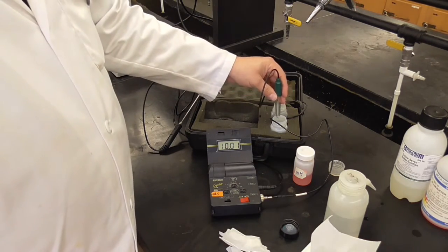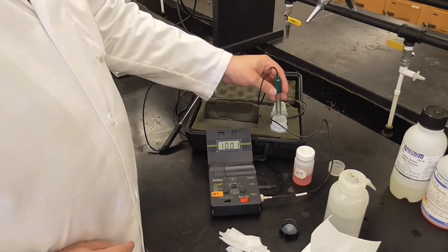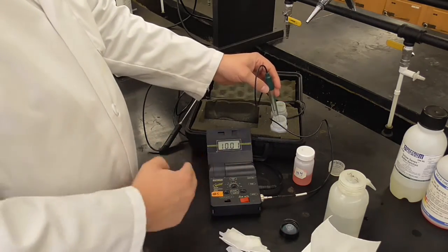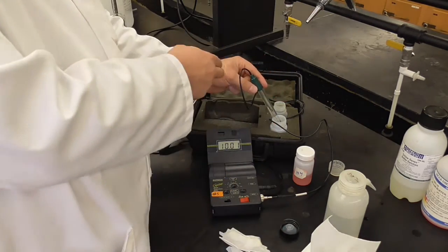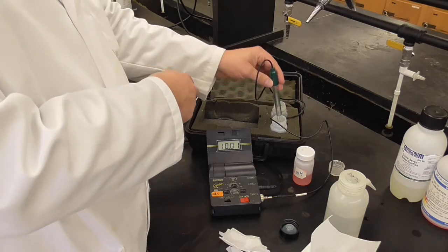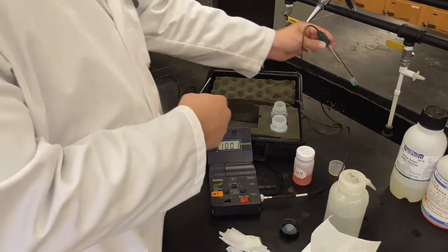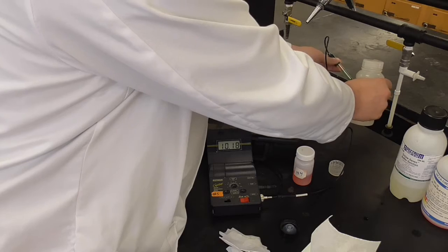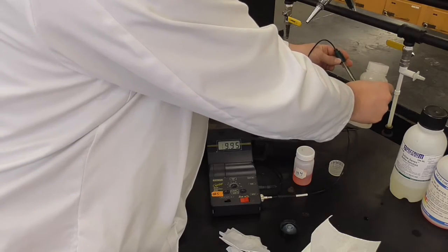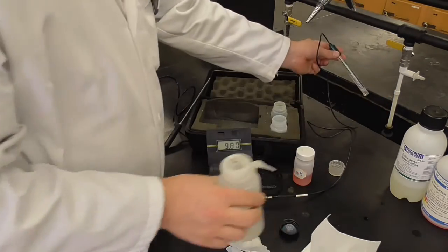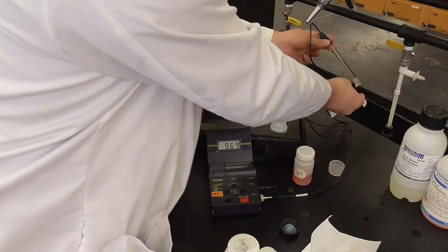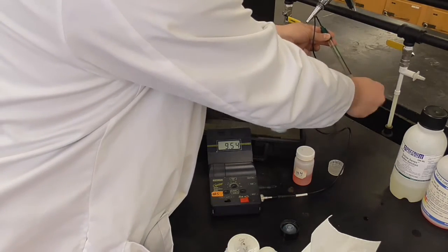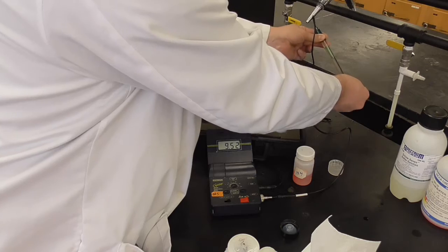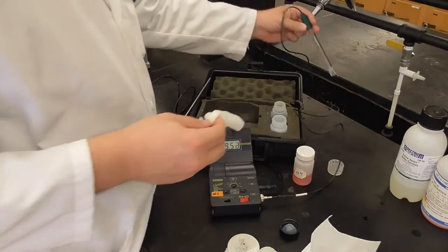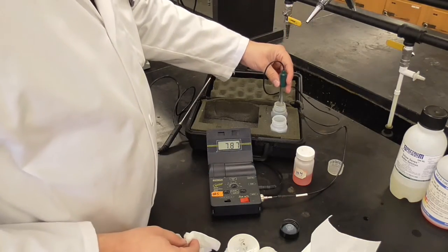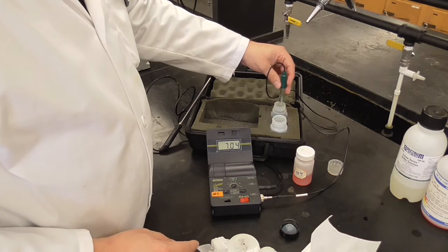Okay, so now you've got the 2 points, you say, okay, I'm done. Well, usually just to double check, because now I've changed both points, what I'm going to do is rinse it, put it back in the pH 7 buffer, make sure it goes back to pH 7. Okay, so again, I rinse off the pH 10 buffer. Again, I'm going to dab off the water here. The majority of the water off. And then I'm going to stick it back in the pH 7 buffer, and it should go back to pH 7.